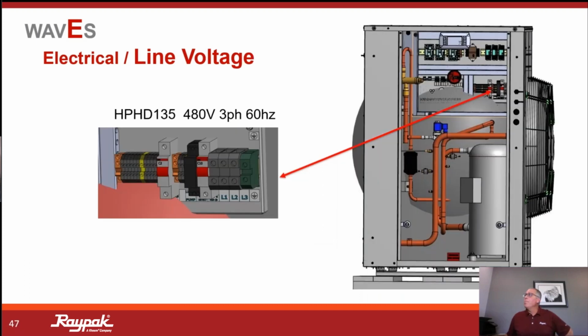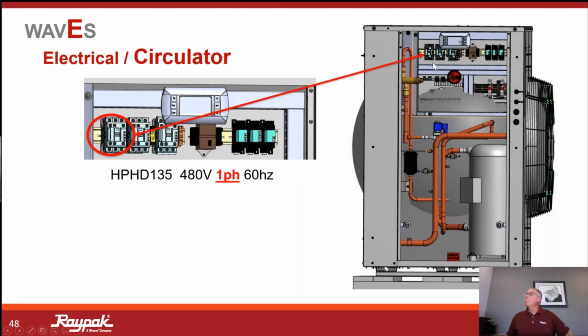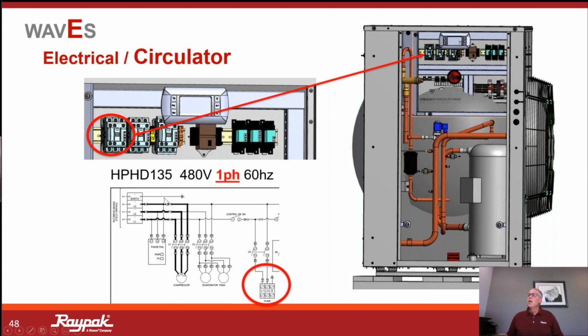Okay, on the larger unit, that is 480 volt 3-phase. So similar in proximity to the 60, but on the 135, the terminals are just a little bit farther to your right, but again, very easy to access, very straightforward. The circulator is, again, up on this top left, dry contacts. Think about it as a definite purpose contactor, if you will. So at present, this is what your wiring will look like going to that circulator.